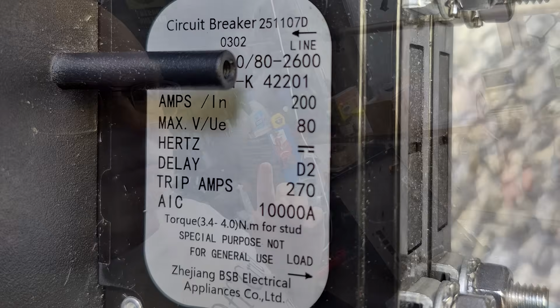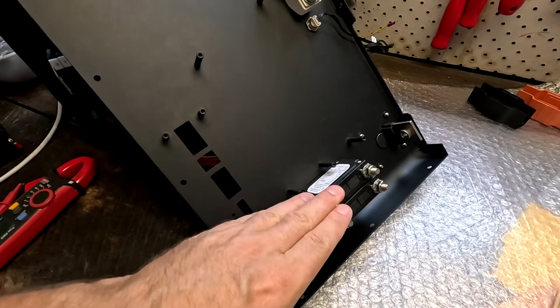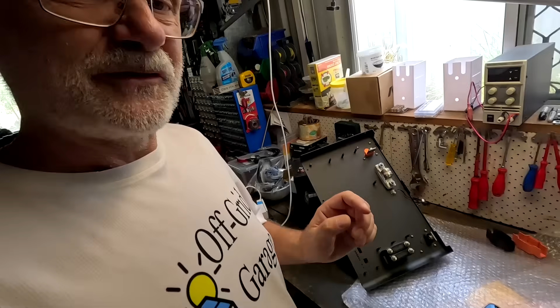And the interruption current is 10,000 amps or 10 kiloamps, which is, by the way, not enough for such a battery. This is a 280 amp hour battery, and the internal resistance is so low there will be more than 10 kiloamps flowing, so this circuit breaker will not be able to interrupt the current. But we still have the fuse here with 100,000 amps of interruption current, and this is clearly capable of interrupting the current. So in case of a short, you may have an arc in here, but the fuse will definitely protect your whole circuit. So from this perspective, I think the choice is fine, because we have two levels of protection, a fuse and a breaker.